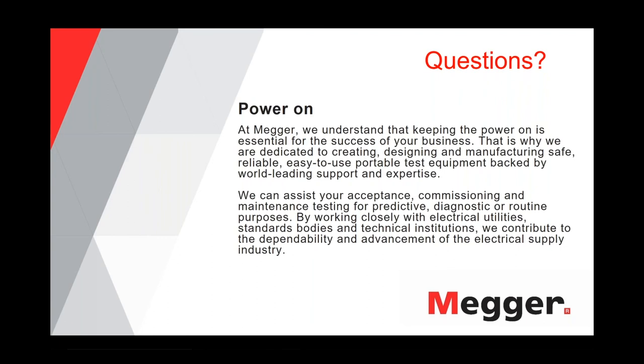You saw some three-phase cable diagrams, and many times one phase is different from the other two phases. So even if the cable was installed at the same time, one phase has a different tan delta than the other two phases. So there is not such a per year increase that can be used. Maybe I can go on to the other question here.